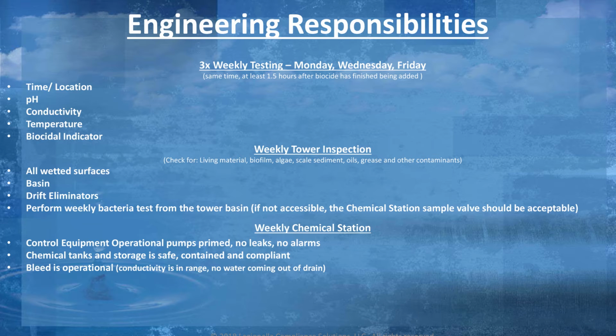Moving along, the responsible person must visit the chemical feed station on a weekly basis to ensure the controller is working and the system is not in alarm. There should be no leaks from pumps, chemical tubing, drums, tanks, and chemical piping. Chemical storage must also be correct. Everything should be safe and compliant. You must also confirm that the conductivity of the system is in range, the bleed is operational, and no water is coming out of the drain unless the system is calling for the bleed valve to open. If you find any of these situations not proper, you should contact your water treatment company immediately.